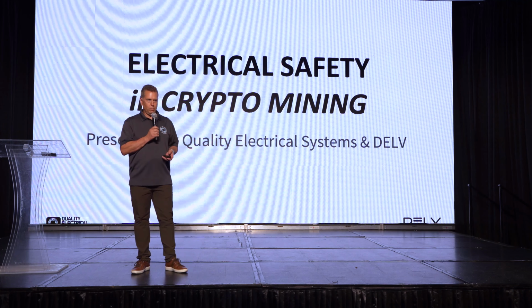When you look at energy like that, it's really interesting. I saw one the other day that talks about just a 22K arc flash. If you're talking about a very typical 480 volt small panel, distribution for a few miners, 22,000 amps of fault current would be fairly typical for a panel like that. A 22K arc flash is about a 250 kilogram shock wave that goes out from it when it flashes. If you convert that to pounds, that's somewhere in the neighborhood of 500. That's about the force that a prize fighter can punch with. So that arc flash is about like getting hit in the face by Mike Tyson.